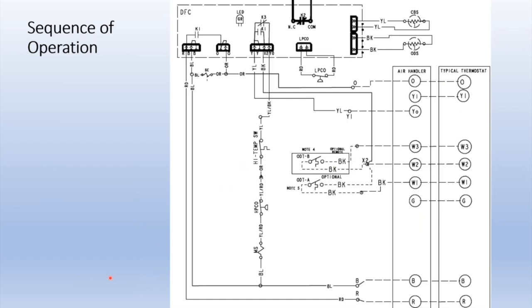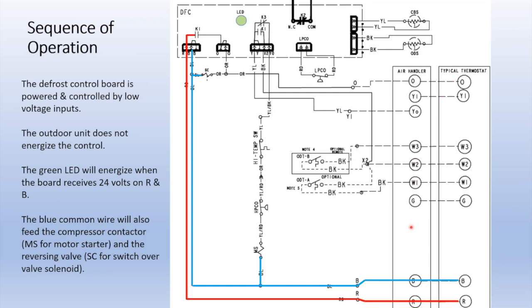So the sequence of operation: we've got our defrost board here, wiring in the outdoor unit here, air handler terminal strip here, and thermostat terminal strip here. First we're going to give it 24 volts on R and common on B, and we're going to see a green LED flash. That's that status light that I pointed out earlier.